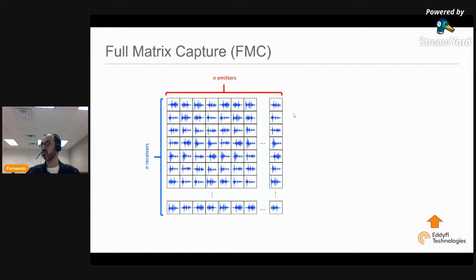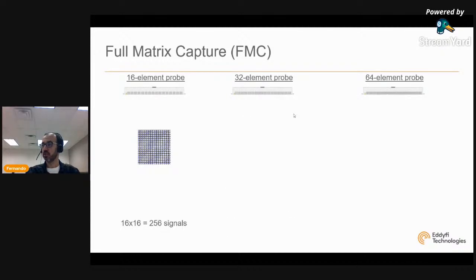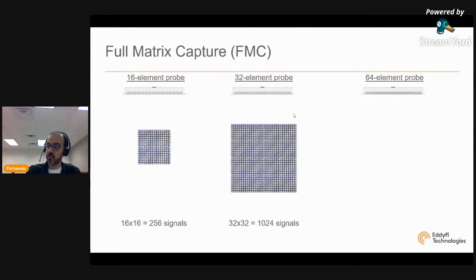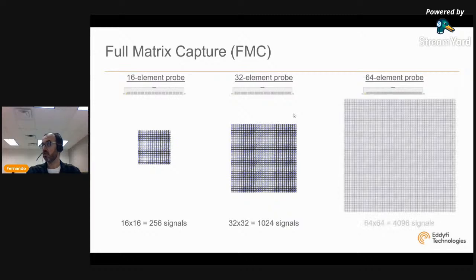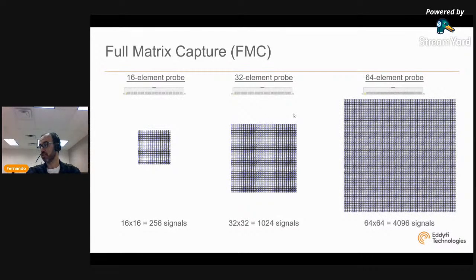So that's the processing for all of them. But depending on how many elements of the probe you have, that's going to tell you how many signals you have. So if you have a 16 element probe, the number of signals that it's going to process is 256 signals. If you have a 32 element probe, it's going to be 1024. If it's 64, it's 4096.